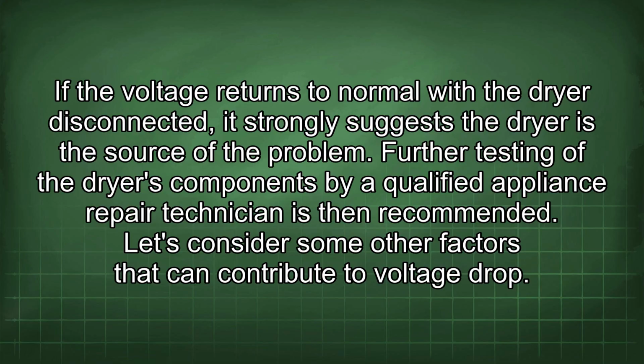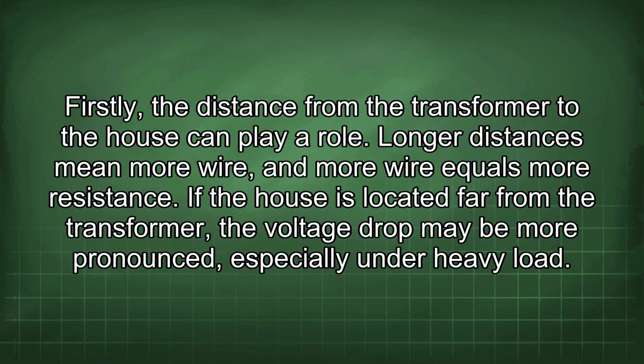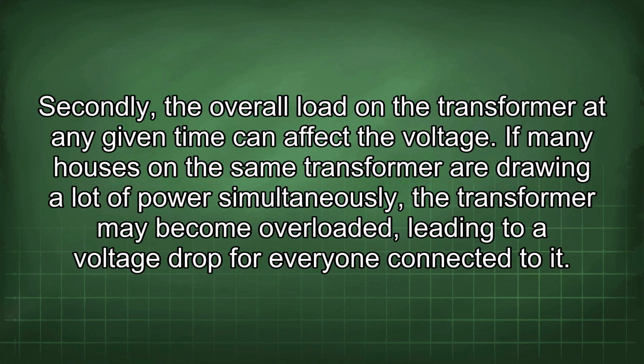Let's consider some other factors that can contribute to voltage drop. Firstly, the distance from the transformer to the house can play a role. Longer distances mean more wire, and more wire equals more resistance. If the house is located far from the transformer, the voltage drop may be more pronounced, especially under heavy load. Secondly, the overall load on the transformer at any given time can affect the voltage. If many houses on the same transformer are drawing a lot of power simultaneously, the transformer may become overloaded, leading to a voltage drop for everyone connected to it.